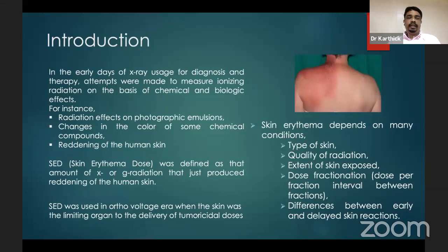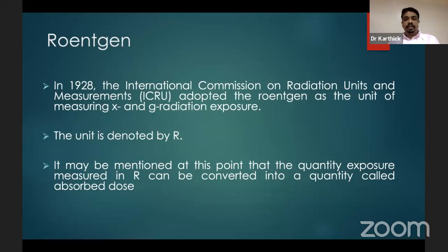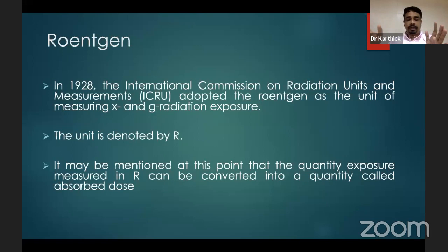Once linear accelerators and megavoltage radiation machines started in the 1920s and 30s, they gradually reduced orthovoltage therapy. In 1928, the International Commission of Radiological Units and Measurements defined a unit called the Roentgen for measuring X-rays and gamma rays. We need to be very clear: the unit of exposure is the Roentgen, it can be used only for X-rays and gamma rays, and it must be measured in air, not any other medium. The unit is denoted by R, and the quantity of exposure in R can be converted into other factors using conversion factors.